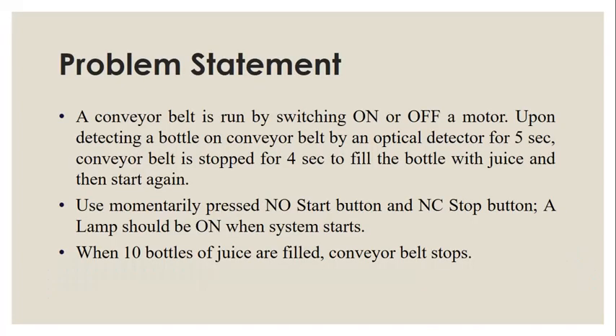The problem statement states that you have a conveyor belt which is run by switching on or off a motor. Upon detecting a bottle on the conveyor belt by an optical detector for five seconds, the conveyor belt must be stopped for four seconds to fill the bottle with some juice, and then it should start again. You have to use a momentarily pressed normally open start button and a momentarily pressed normally closed stop button. A lamp should be on whenever you start the system and remain on until the system is running. Additionally, if 10 bottles of juice are filled, the conveyor belt must stop as well.